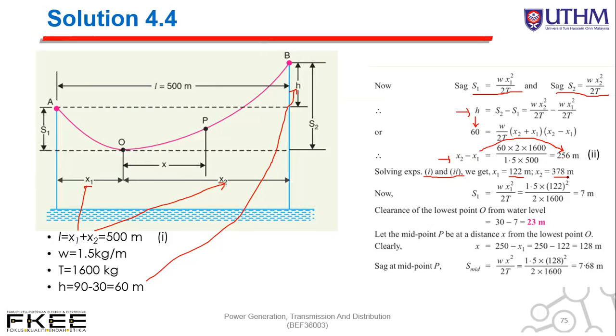Alright. Then we can also calculate S1, using X1 from the calculation. So we get S1 equal to 7 meter. Then the clearance of the lowest point O from water level must be 30 minus 7. So it will be 23 meter, right? Because S1 is 7 meter and the tower is 30 meter. So the clearance is 23 meter. Is it okay or not?